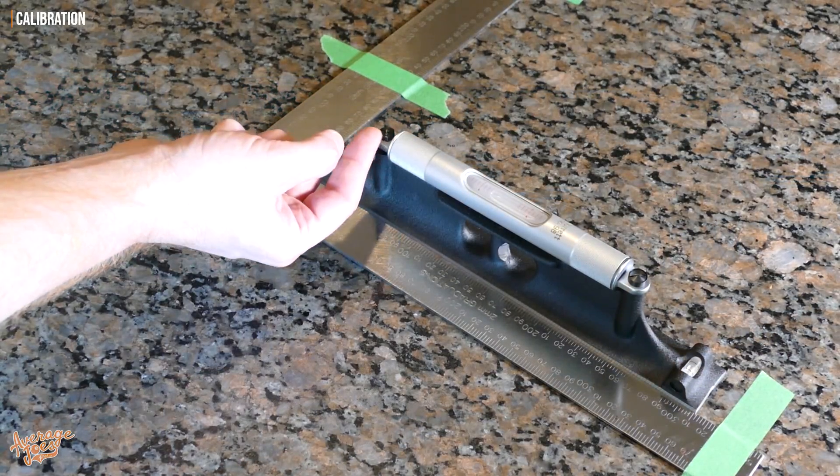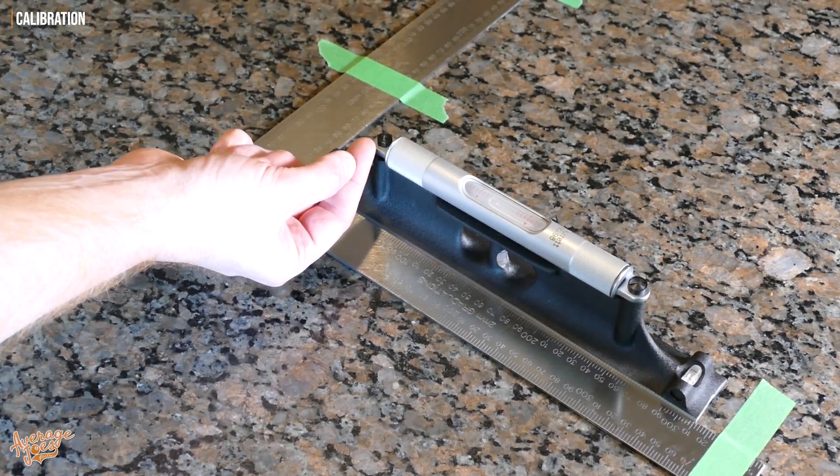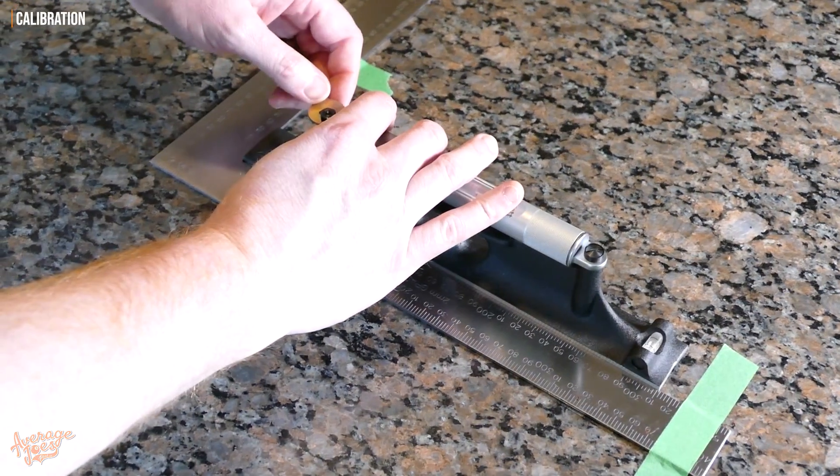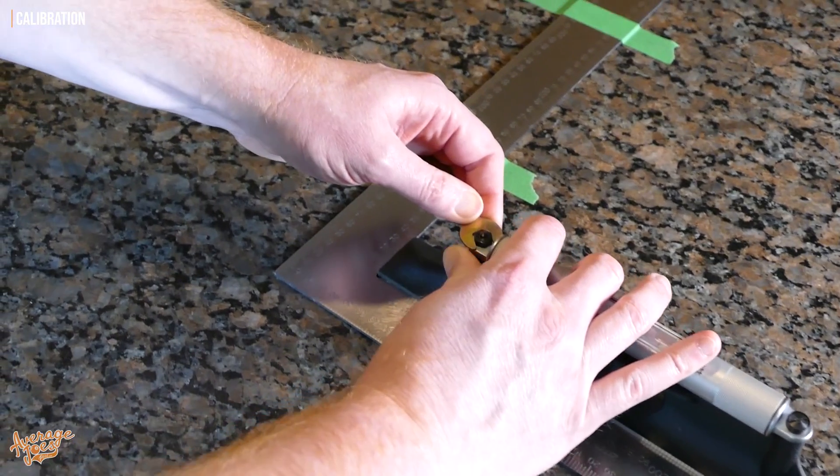So what we need to do is undo that, and then we're going to use the lower nut to raise it up and down to get it level. Then once we're happy, we'll lock it back in place with the upper nut. So we'll go ahead and get the upper nut undone.